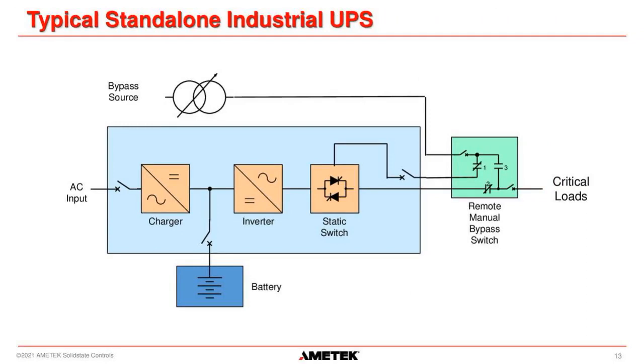So this is the diagram of our UPSs. Our UPSs are online UPSs that have an integrated charger, inverter, and a static switch. Those are the three main parts of our UPSs. The charger rectifies the incoming AC voltage to DC, and then the battery connects to this DC bus, which then feeds the inverter to convert the DC back to AC. And then we have a static switch to switch between the bypass source for the load and the UPS source.